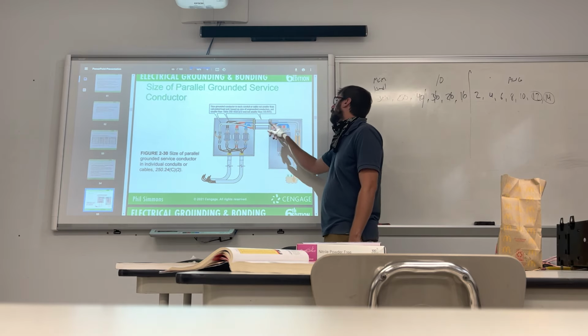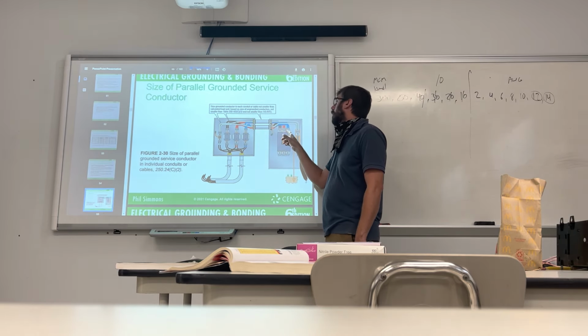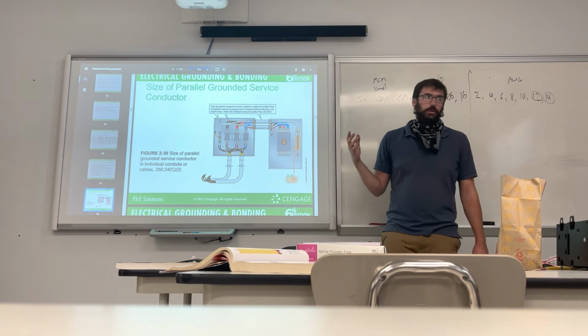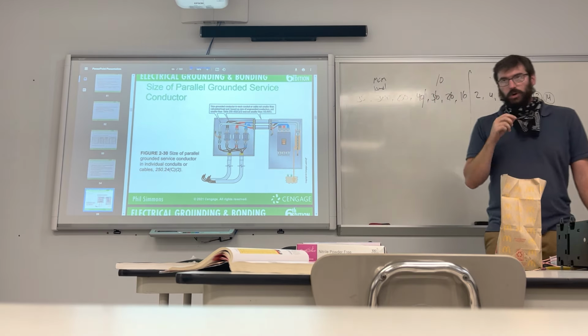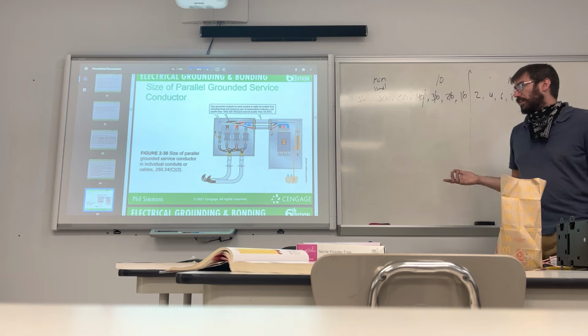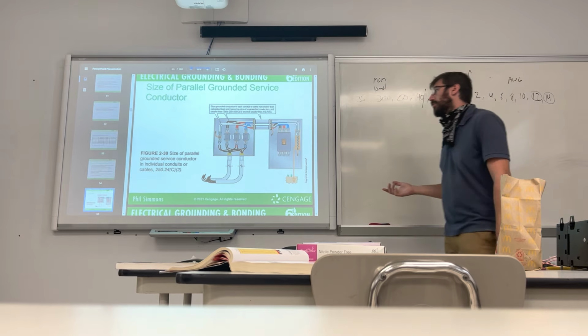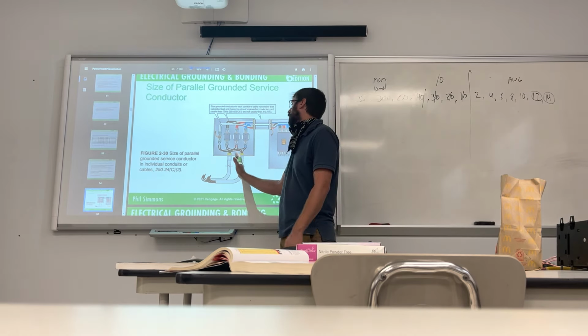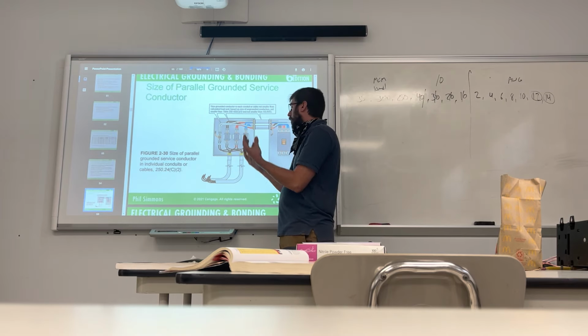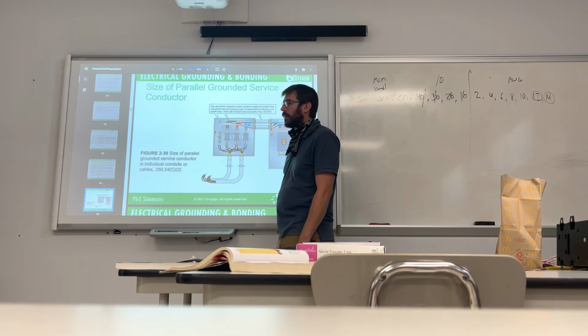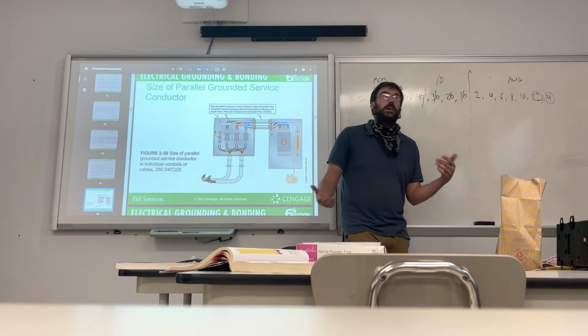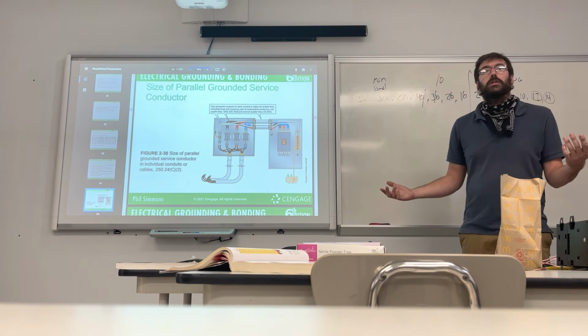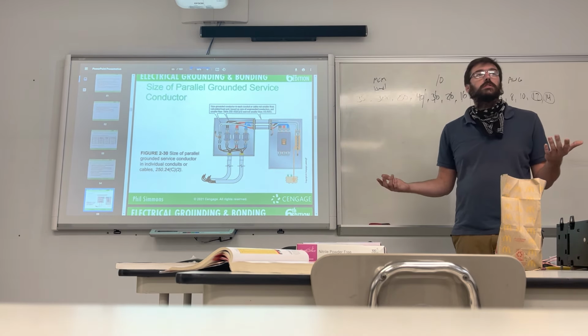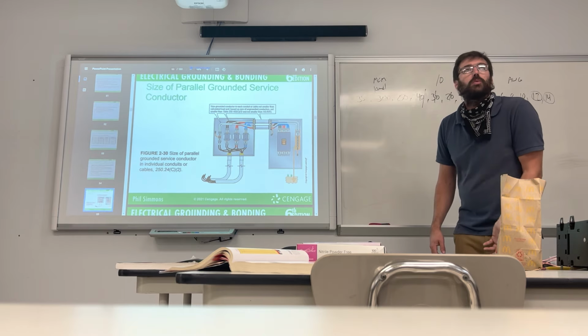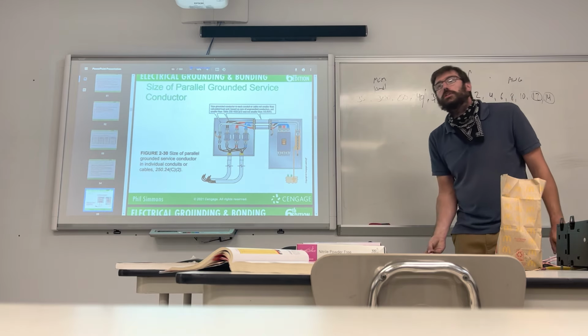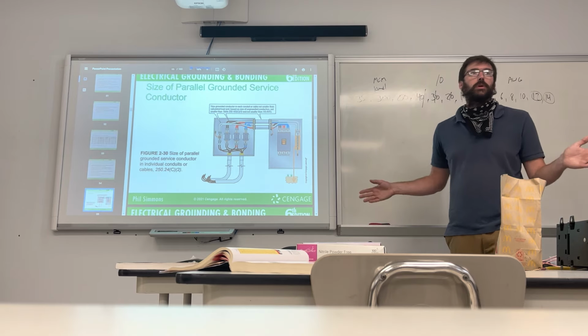So these are coming in, they're buddying them up. But there has to be a neutral line that goes through with those three. We're going to start to build magnetic fields, you can start building current, even with these coming in. It shows a neutral, like it's three wires of the same circuit. I've seen guys talk about having three conduits coming in and buddying up these lines. Why don't I just have a couple lines of line 1 go to the first one, a couple lines of line 2 go to the second one? No, it's going to start building weird current.